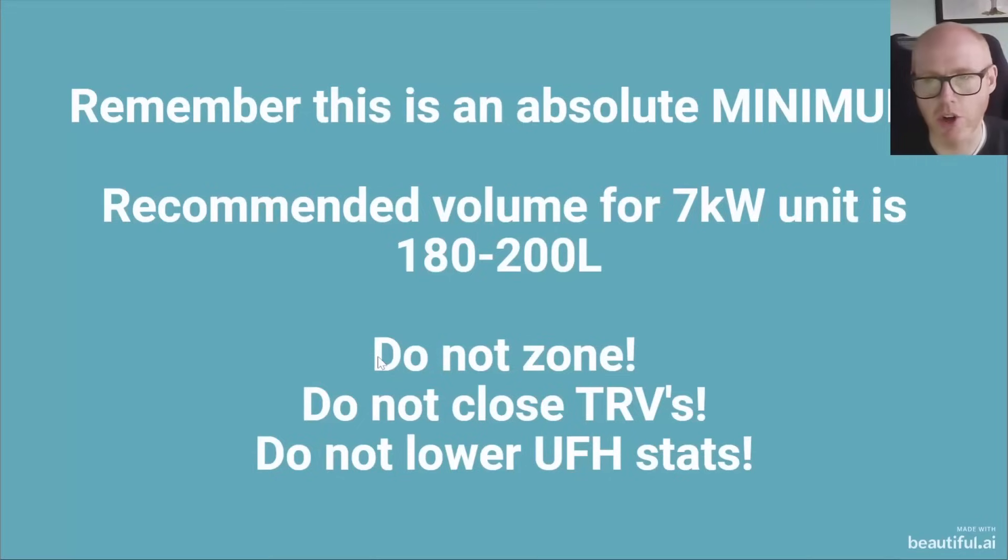It's so important not to zone, not to close TRVs, and not to lower underfloor heating stats, especially when it gets really cold, because you're reducing your system volume and that can really affect how your defrost is happening. It could slow down defrost but also increase the rate at which defrosting needs to occur because your system volume is so small.